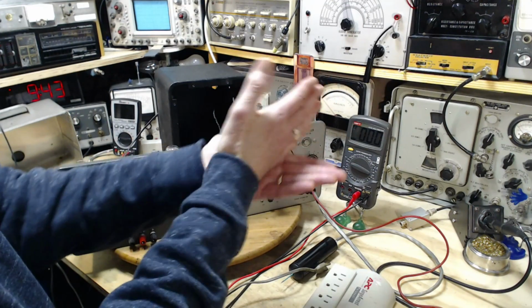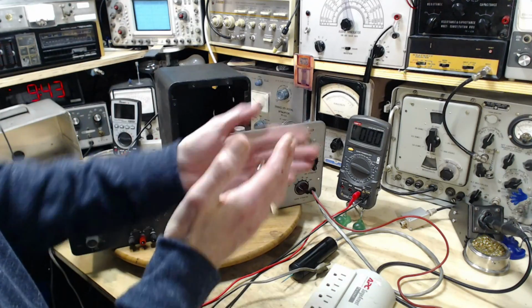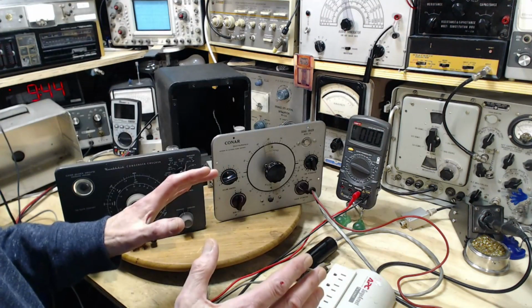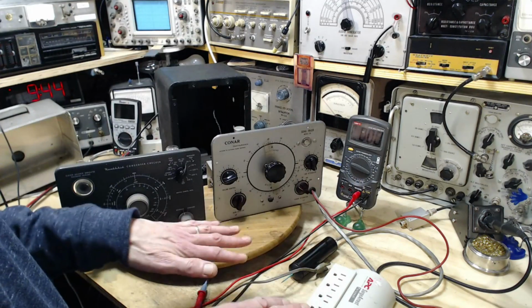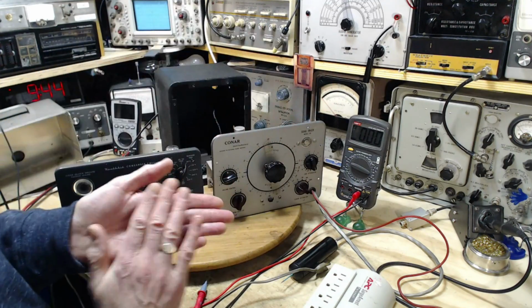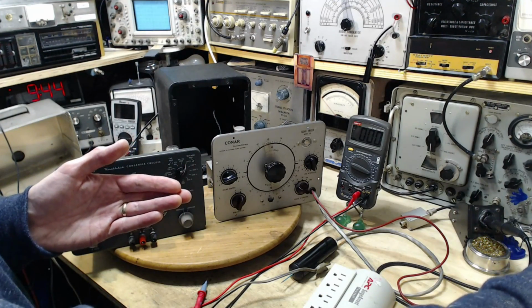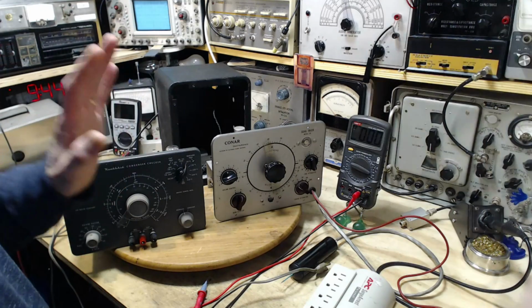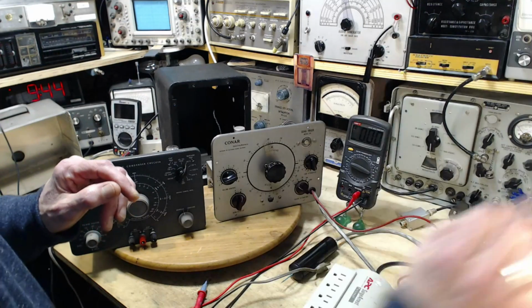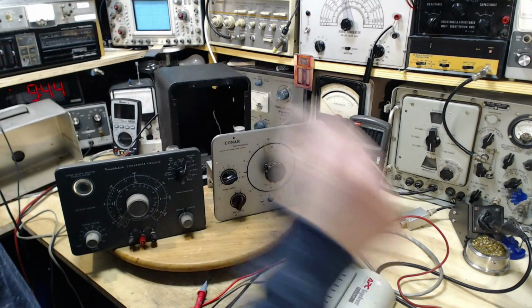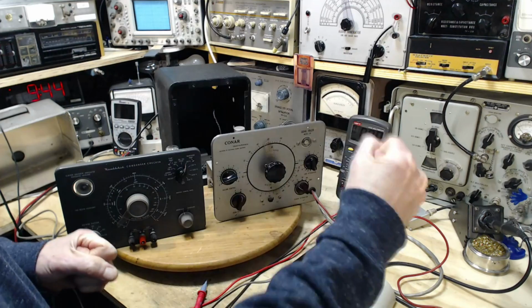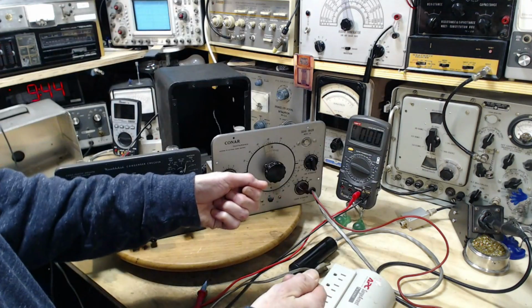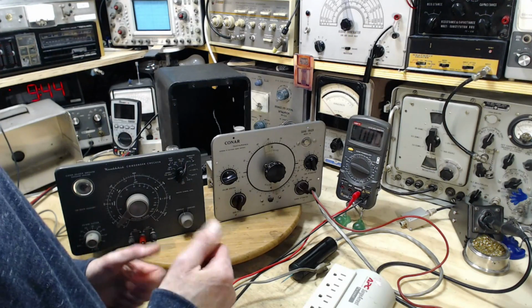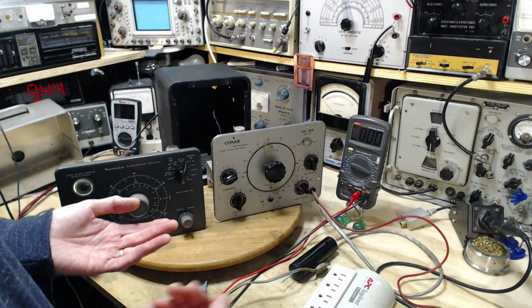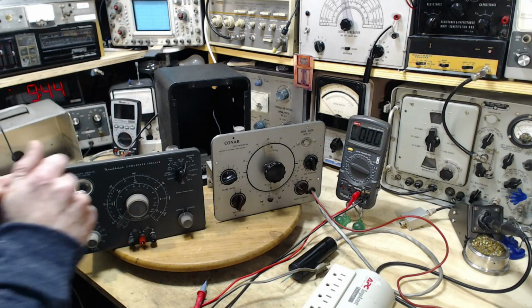Maybe you've got a cable and a pipe in friction, and after 40 years contact is made. Without the neutral connection, your pipes will rise up to 120 volts. Some current will flow out the water pipe into the street, assuming it's all electrically continuous — in some cases it's not, there's bits of plastic pipe here and there. But probably the fuse will not blow in your fuse box. That's the problem: the short circuit remains in place until you find out the hard way that your house plumbing has risen to 120 volts. You will find out at some point, and it won't be pretty.